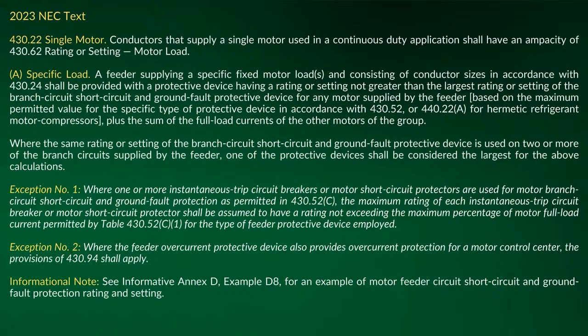And let's just hypothetically say you go to a motor and then you add a hermetic refrigerant motor compressor on there. That's a feeder going over to it. You see what I'm saying? If I go to a single unit, an AC unit, that's a single branch circuit going over. That's not a feeder going over there. And just looking at this section alone tells you what he's saying is not true. And it's interesting too, because let's say you design the whole thing to have a pull out, which is usually what we have on our job sites when we're doing multifamily.